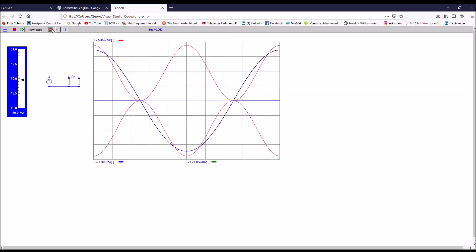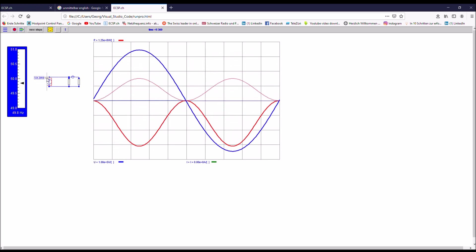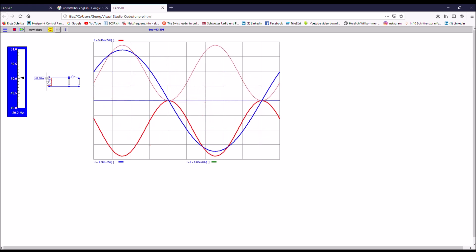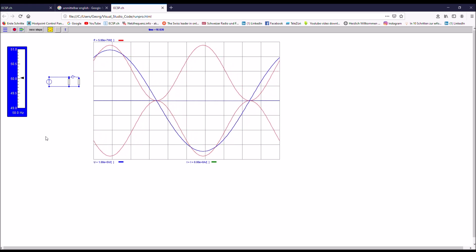Again, we go here and you see now that the frequency remains relatively close to the nominal, even with the change in the load. And so the only thing you have to do now is to adjust the frequency manually. This would normally be done by the automatic grid controller. You see that it's now much, much easier. You switch on the droop and then you have much less stress.